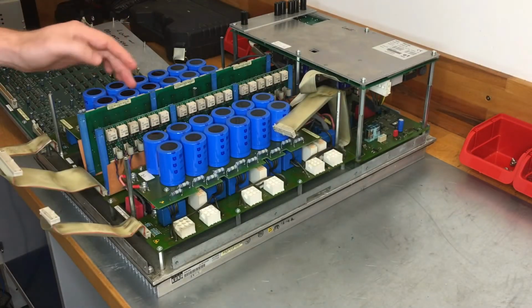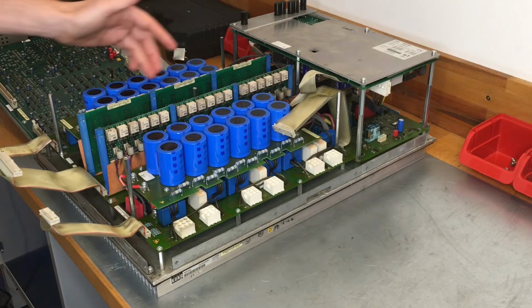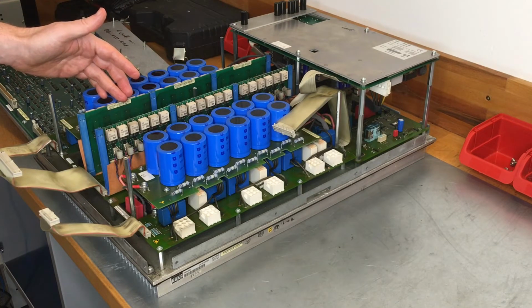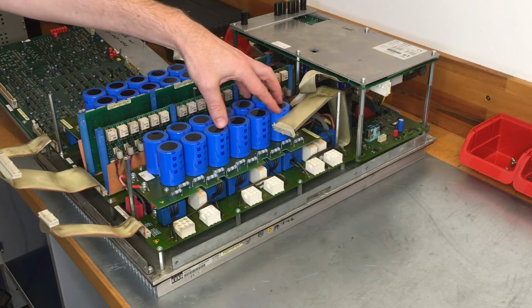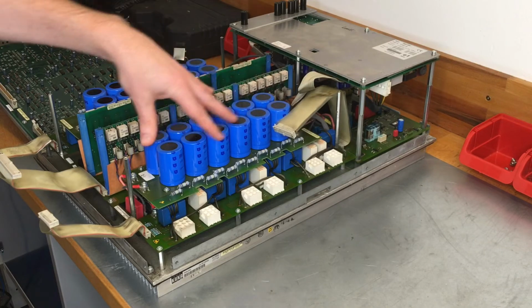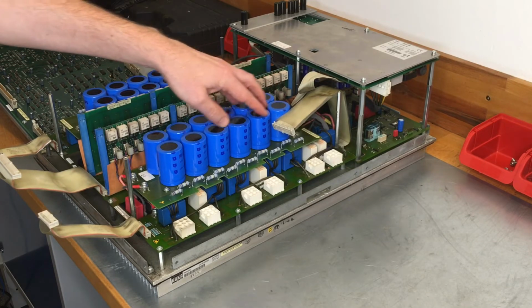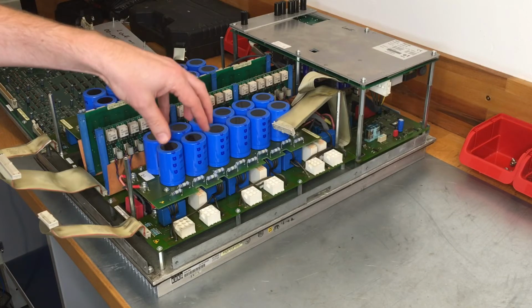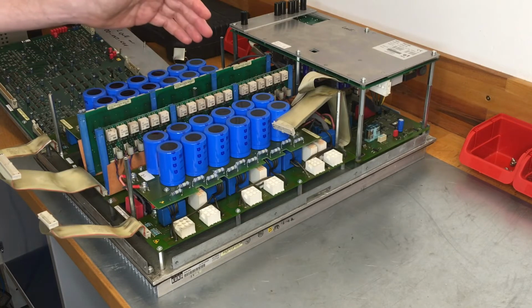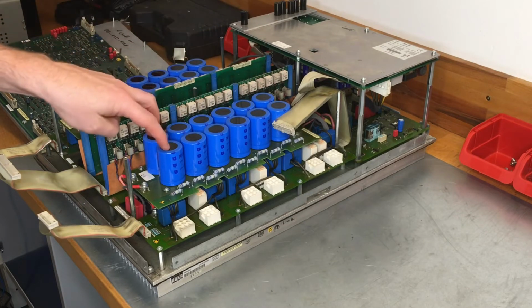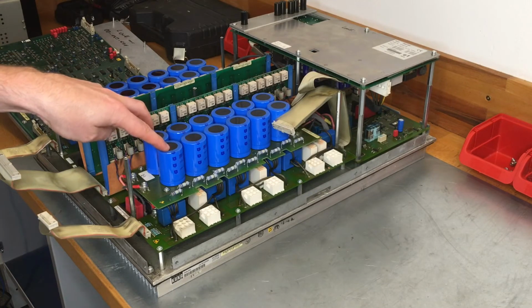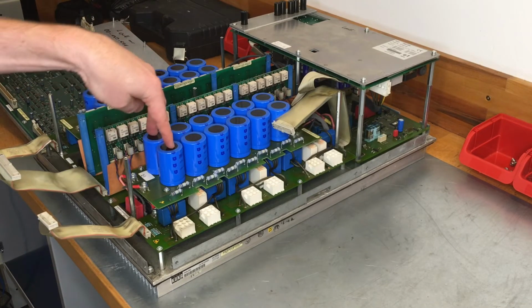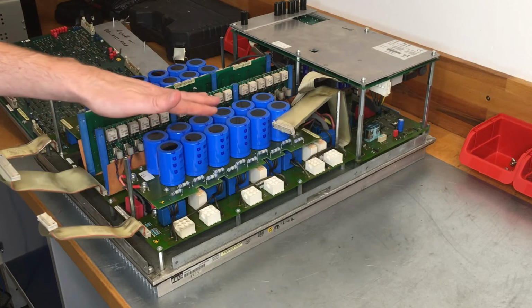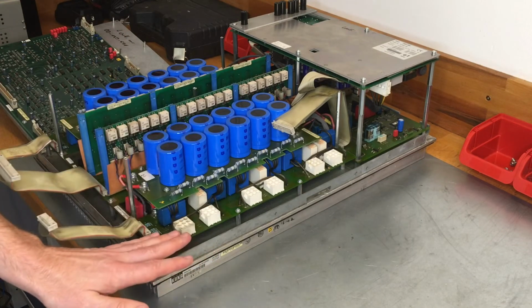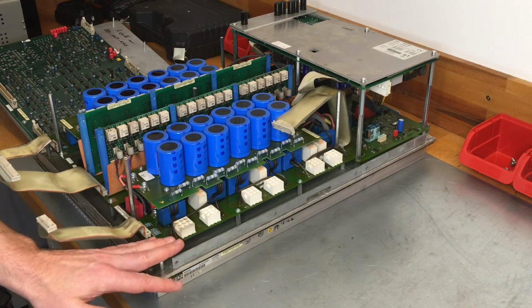What you can see now are the 6 driver cards, each for one of the 6 motors to control the 6 IGBT bridges. You can also see these mighty electrolytic capacitor boards that are intended for smoothing the DC link voltage. Don't be surprised if you see a couple of capacitors more than usual. I added 2 more for testing purposes, because interestingly there is an additional space provided. Underneath is the so-called mainboard, which I'll come back to in a minute.